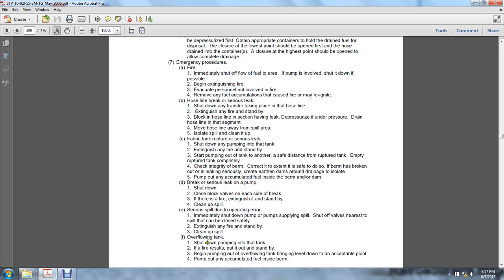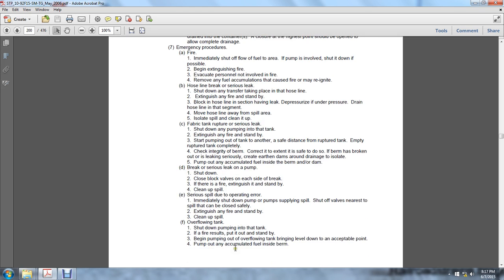Overflowing of the tank. Shut down the pumping into the tank. If a fire results, put it out and stand by. Begin pumping out the overflowing tank, bringing the level down to an acceptable point. Pump out any accumulated fuel inside the berm.